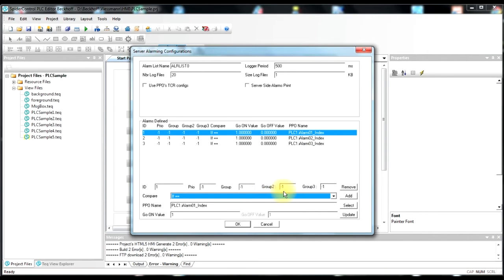and the logger will, as soon as it has received such a configuration, start with logging these alarms. What is important about our technology is that it is flash memory friendly, so the alarm logging should not write constantly to the flash file system, otherwise it would be damaged. So what we do here is we record the new incoming events to a RAM buffer, and only when the buffer is full it will be written in one complete file.